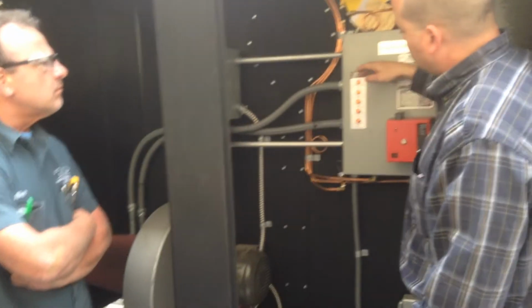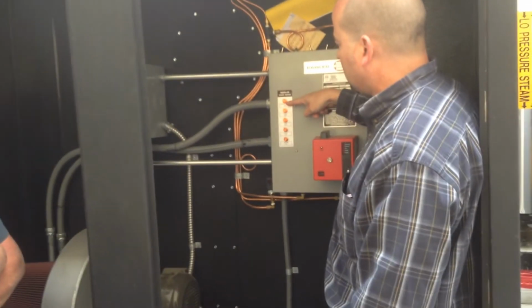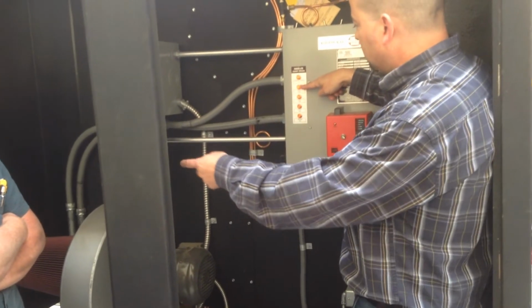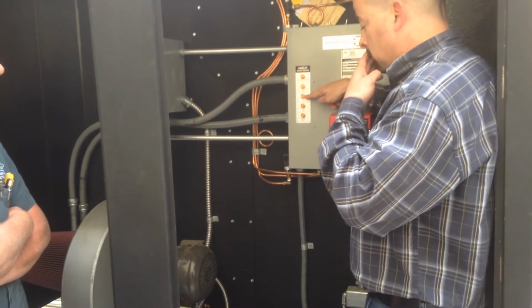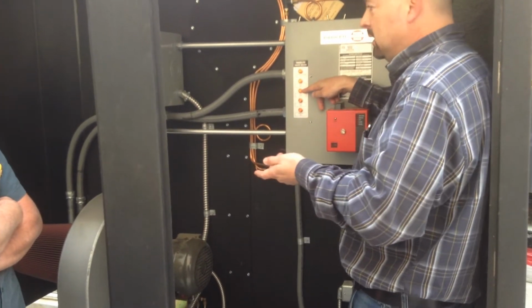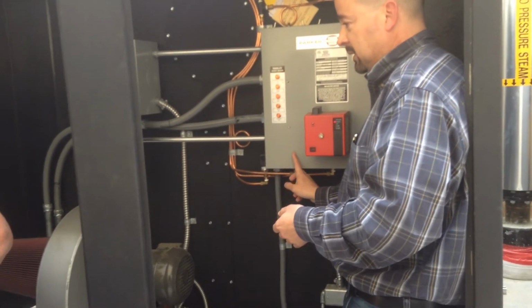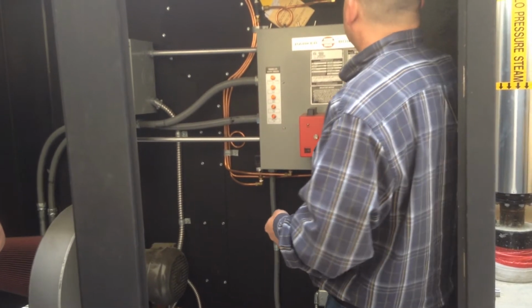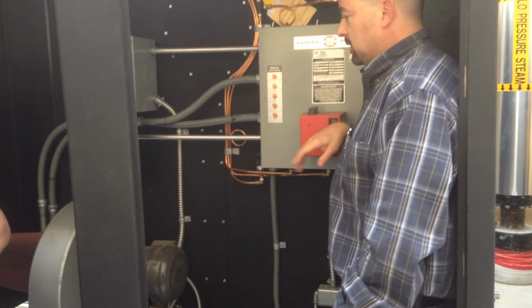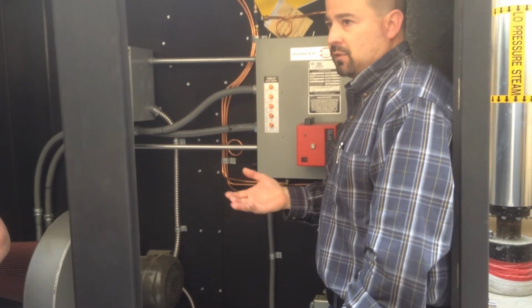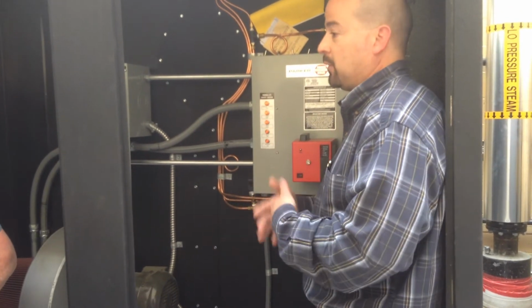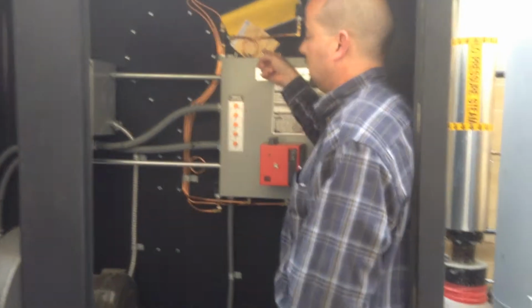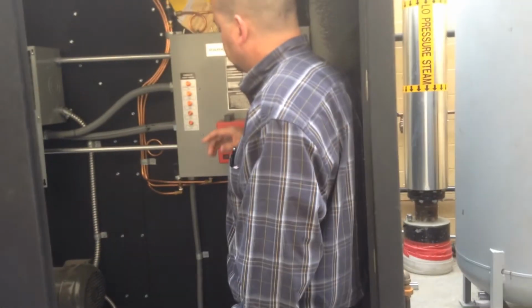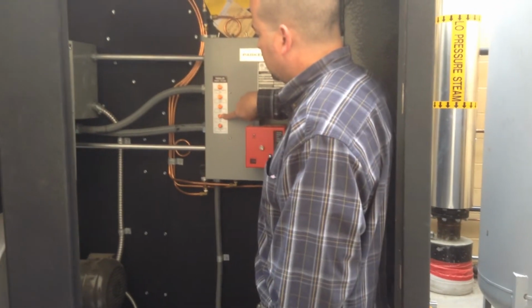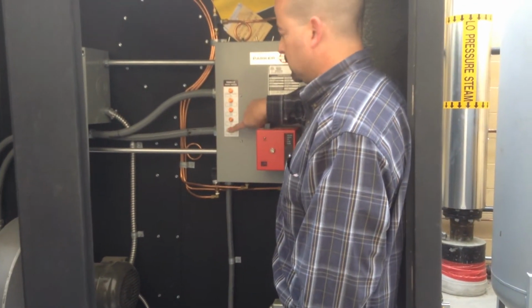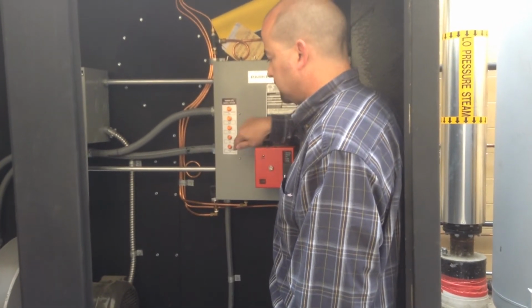And then this too is from top to bottom. So, control power on, level safe, limit safe. Excuse me. A limit is anything. It's the manual reset high limit, it's the automatic high limit, it's the operating control, it's any of your switches or safeties. So it's saying, okay, limits are safe, I'm ready to fire, but it's not firing because I have the burner switch off. And this is pilot on, and this is burner on. So whenever you have flame, this one will come on.